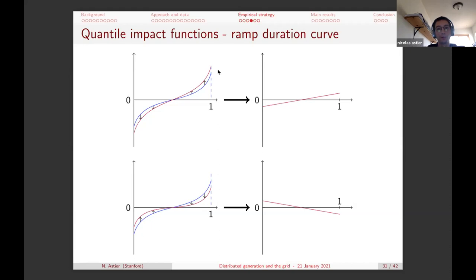So again, blue would be the historical ramp duration curve and purple how it changes once you have added 1 megawatt of a given distributed generation technology. And so if you tend to make extreme ramps worse, and so you shift the ramp duration curve in that direction, you end up with an upward sloping quantile impact function. And that's bad because that tells you that the extreme ramps, both positive and negative, are exacerbated by the addition of this megawatt of distributed generation. And what you're hoping for is a downward sloping quantile impact function because it tells you that the addition of the distributed generation unit tends to decrease the extreme ramps you observe on average at the substations.